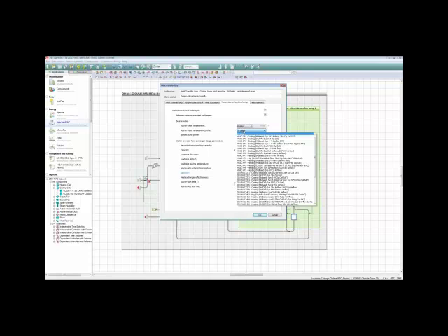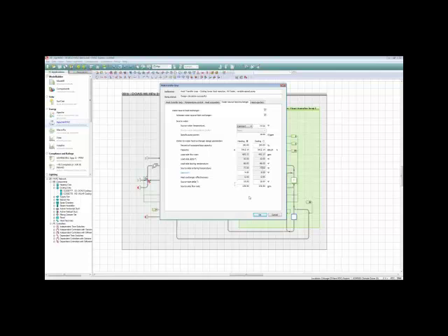Then approach values and things like that. This assumes you get the same piece of metal, so you're setting it in terms of the heating or cooling selection of the device, but you're not really setting it for both of those independently, because you don't really have two different devices. But you can change the source side delta T, which is linked to the source side flow rate. You can say, oh, I'm going to adjust the source side flow rate, and that then will adjust the delta T for you. Those are linked, and the little bar there is just indicating that.